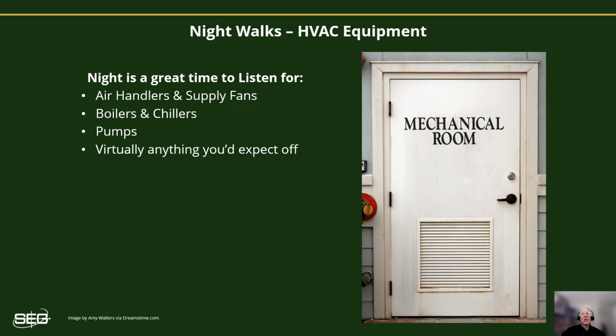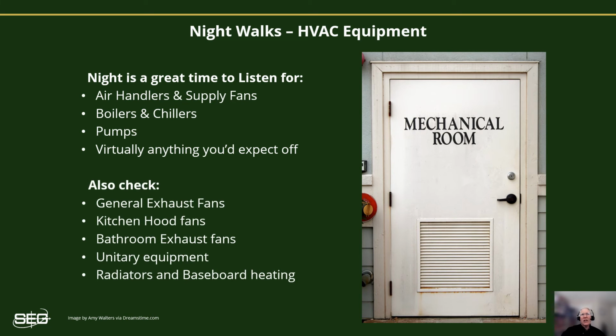Night walks are a good time to check the mechanical rooms for equipment that's still running, like air handlers, fans, boilers, chillers, and pumps. Can you find any general exhaust fans, bathroom exhaust fans, or kitchen hood exhaust systems that are still running? These systems are occasionally overlooked and never tied into the automated control systems, even if it's part of the installation contract. These systems could operate 24/7 for years before anyone notices it. Also realize if fans continue to run when the rest of the HVAC is turned off, they're exhausting your energy outdoors, essentially throwing conditioned air right out of the building.